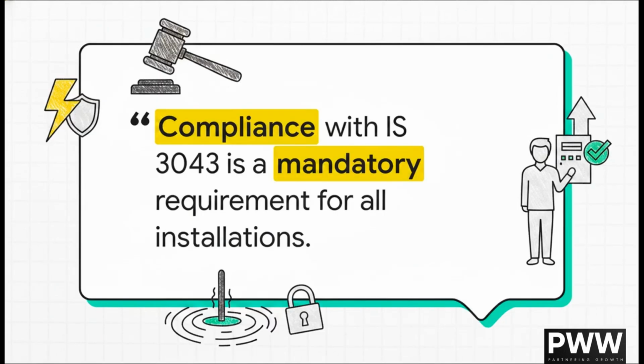Now, here's where things get serious. This isn't just best practice anymore, guys. It's the law. The Central Electricity Authority's 2023 regulations have drastically shifted the landscape here in India. As this regulation highlights, compliance with IS 3043 is a strict, mandatory requirement. The focus has completely moved away from just trying to hit some arbitrary low resistance value, like blindly aiming for a generic 1 ohm. Instead, the law now demands rigorous safety analysis to genuinely ensure human safety under fault conditions.